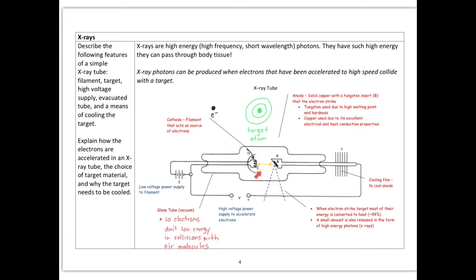So, opposite this cathode filament, we have our target, also known as our anode. And what we do is we apply a higher voltage, normally several thousand volts, between the cathode filament and this target. This would be the positive end, the target. The negative end is the filament, which causes the electrons to be repelled from the negative and accelerated towards the positive at very high speed. So the electrons slam into this target here, which is this dark bit indicated by B.